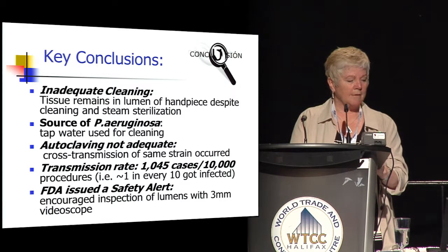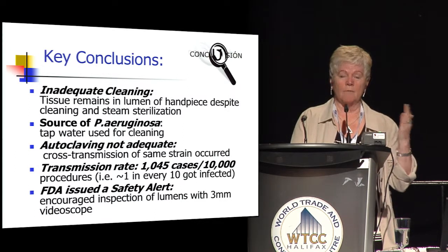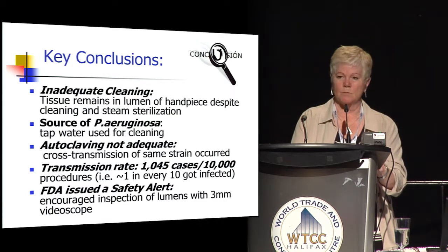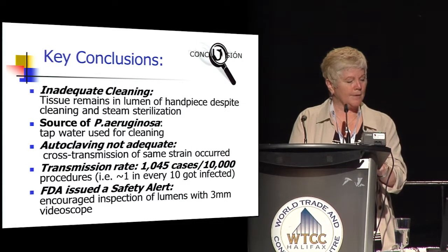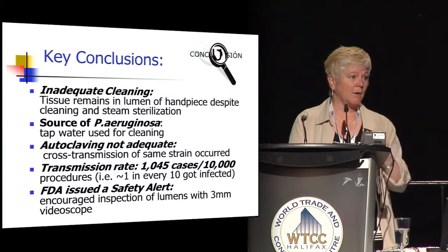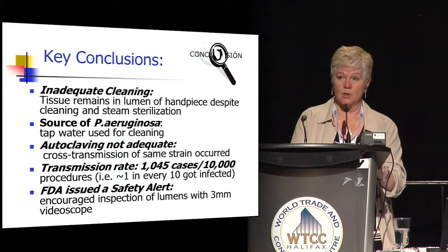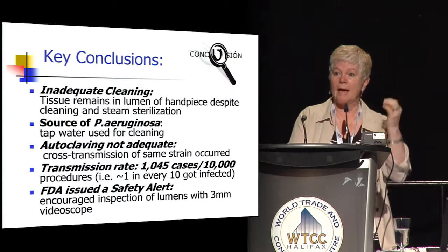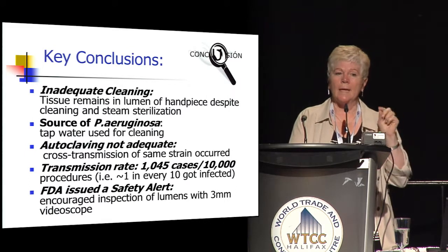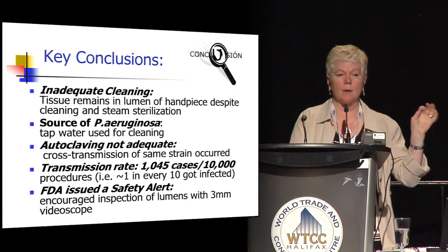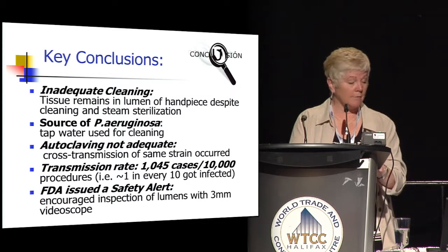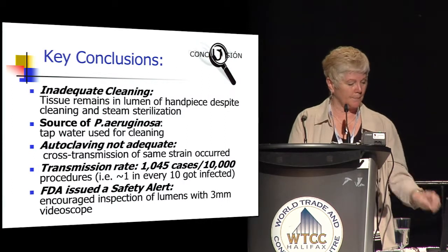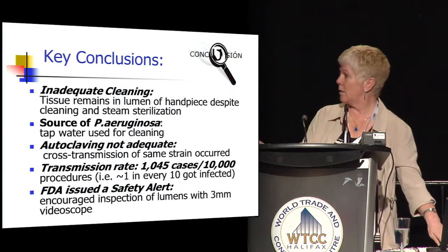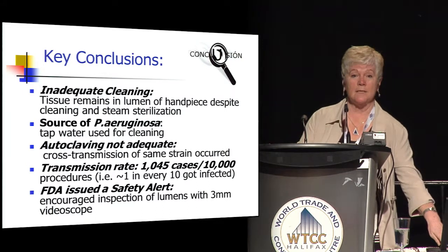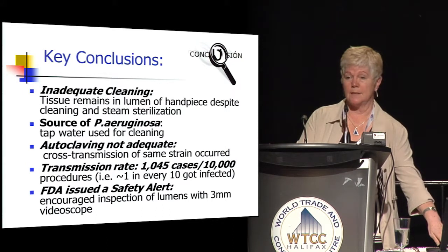Now, the autoclaving was not adequate, and that was obvious from the transmission of the same strain occurring. And the transmission rate was 1 in every 10, and that's an extremely high rate for a medical device for transmission of a bacterium after steam sterilization. So again, you can see with both of these examples, the transmission rates are actually very, very high when they have outbreaks.